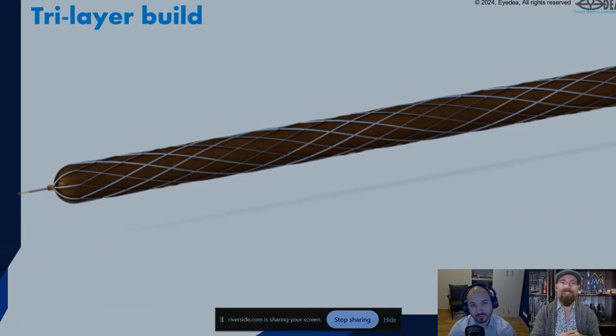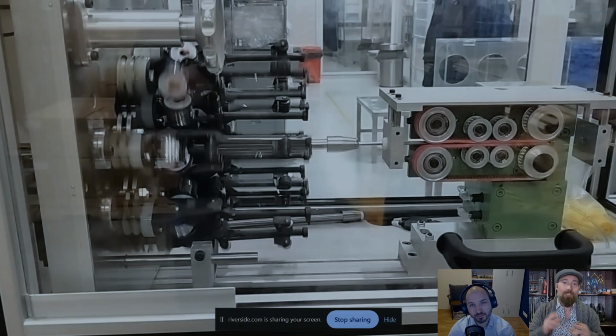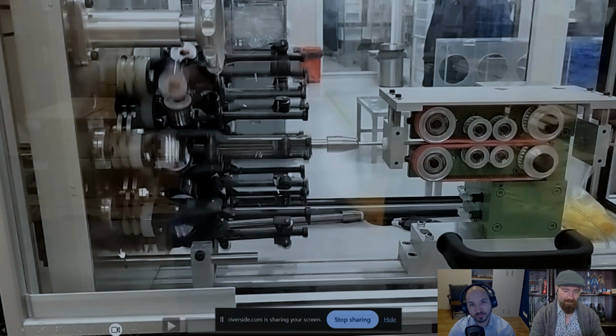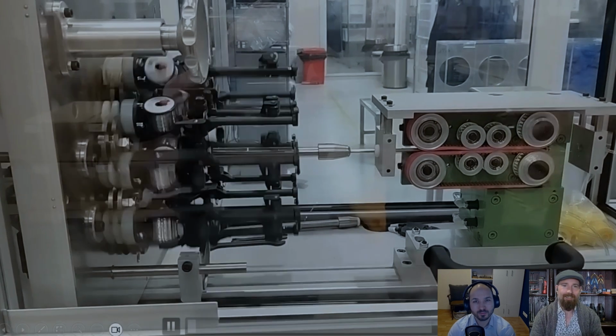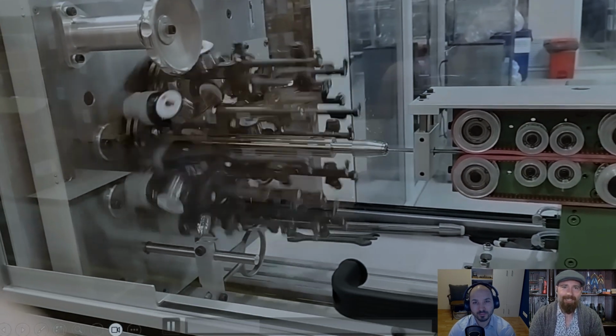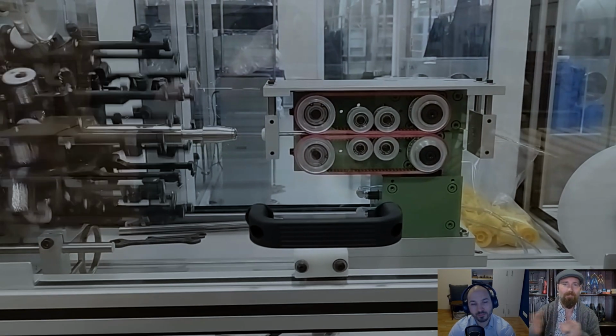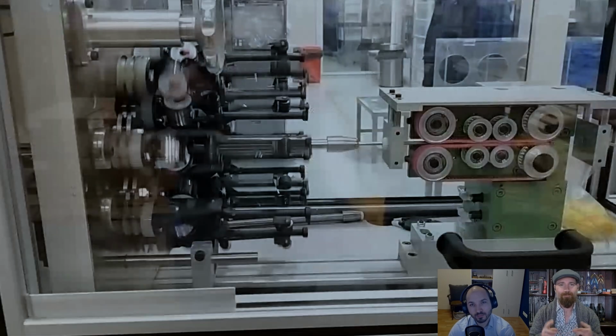Next thing we have to do is put essentially a skeleton into the device. And this makes sure that it's very strong, durable, keeps the circular inside circular, stops it ovalizing. And then if some parts of the device breaks, this also is our fishing line to help get the device out. So this goes through a braiding machine. Braiding machines are, as you'll see here, in real speed. The bobbins are spinning fast, the device is moving slow. This could take 10, 15, 20 minutes for one device to go through from one side to the other.